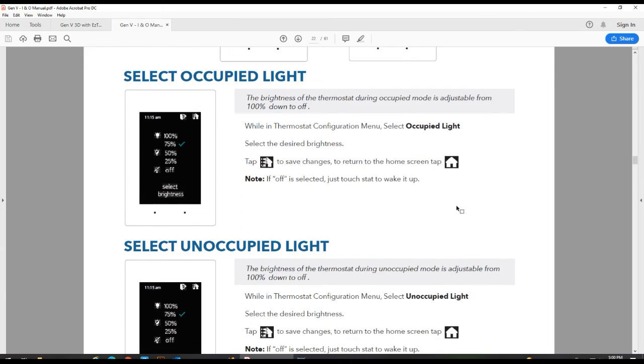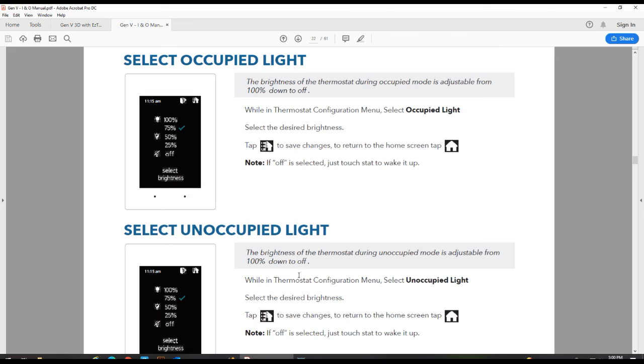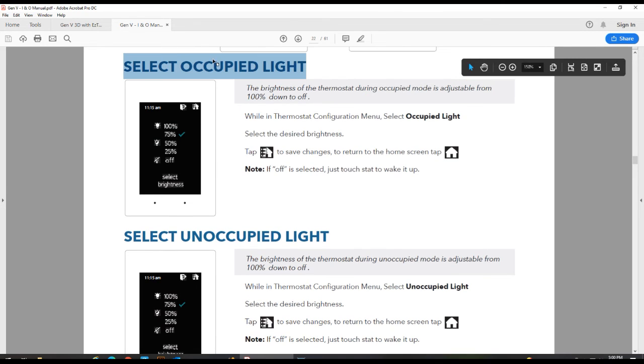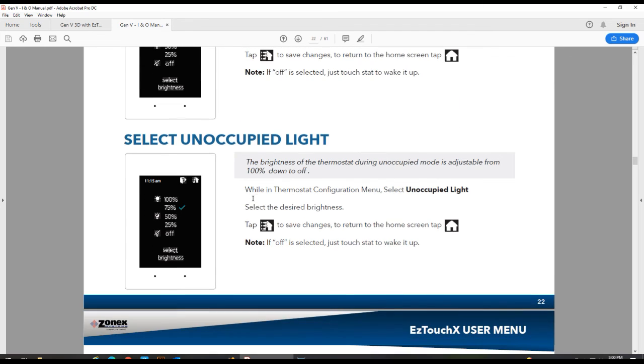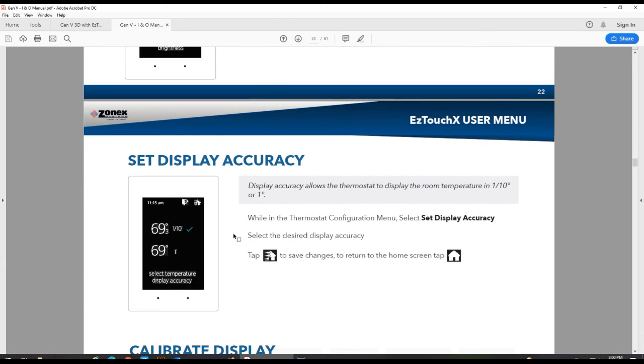If you want, there are backlight settings or adjustments we can make. So for the occupied light, we can adjust the brightness anywhere from 100% to off if the stat seems to be too bright for the end user. During unoccupied hours, if you so choose, you can set the unoccupied backlight to a different brightness and or off. A lot of contractors like to set it to off because it will extend the backlight. So if you want to do that, go ahead and make those changes.